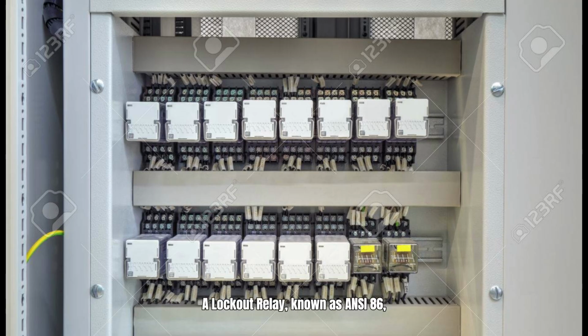A lockout relay, known as ANSI 86, is fundamentally a mechanically latched relay designed to operate decisively and permanently trip and lock out circuit breakers in response to a severe or critical fault condition within the electrical system. Once this relay has operated and latched into its tripped position, it remains in that state, ensuring the system stays isolated until a qualified operator performs a manual reset, thereby preventing any automatic re-energization that could lead to further damage or hazards.